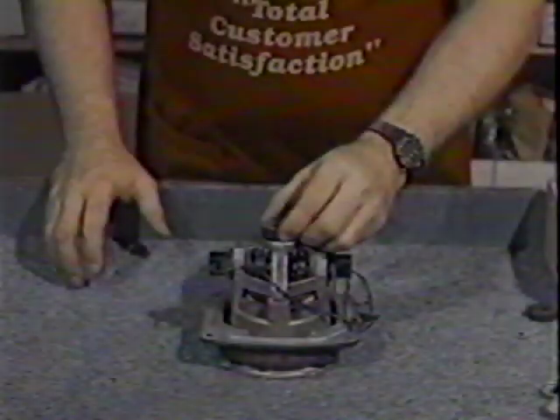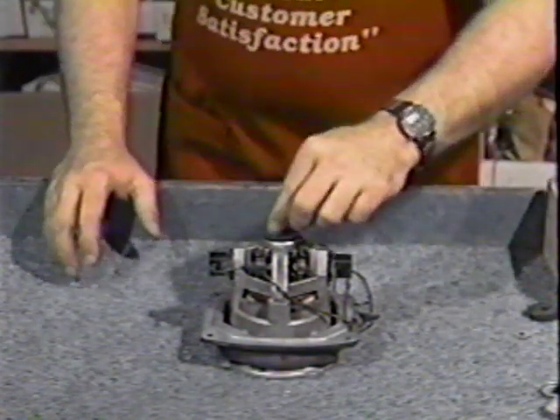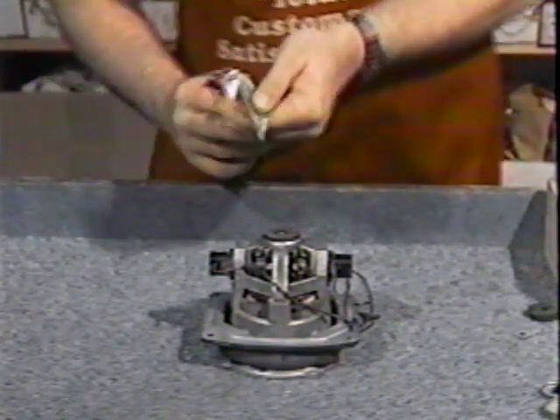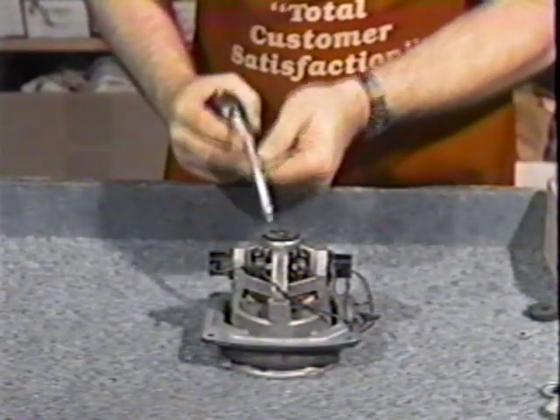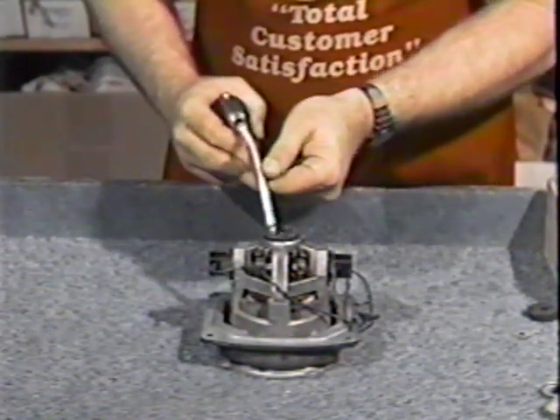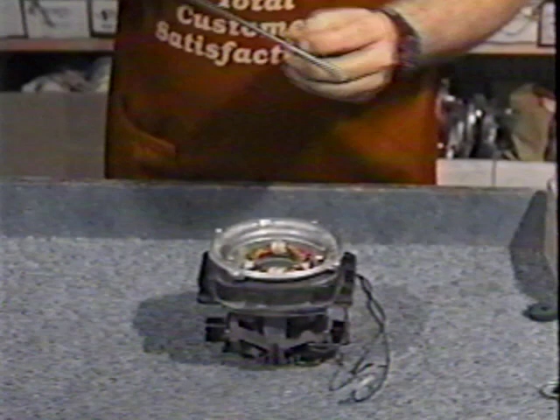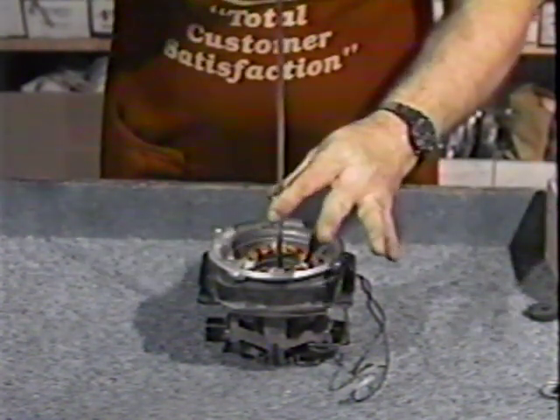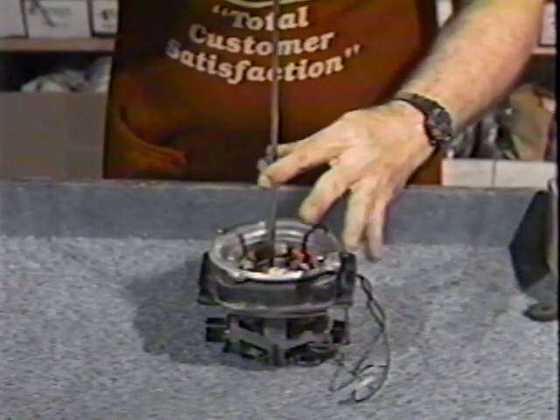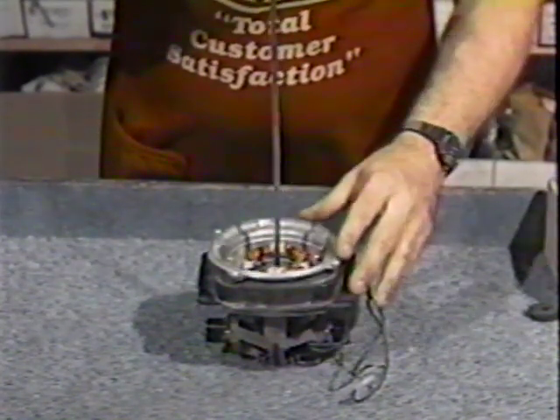Next, place a new felt pad into position. Apply 3 to 5 drops of 30-weight oil and secure the top cap. Finally, place a new spacer into position and install the lower cap. The motor is then reassembled in reverse order of disassembly.